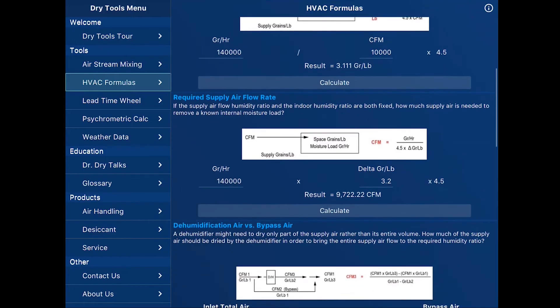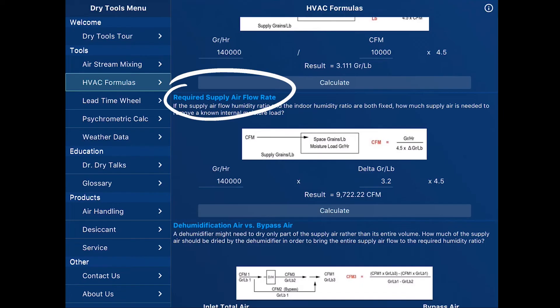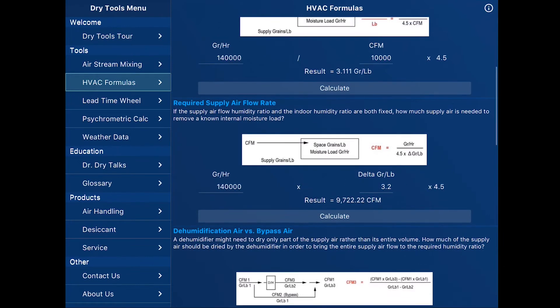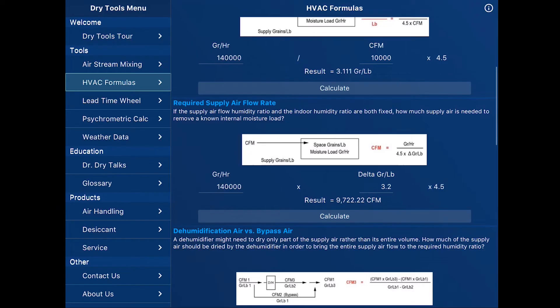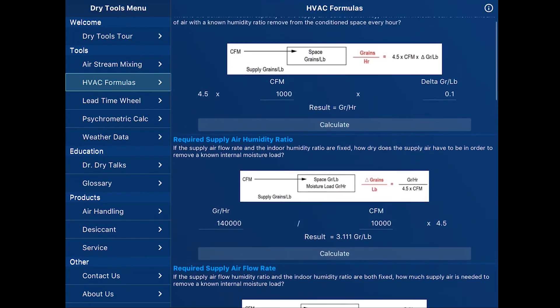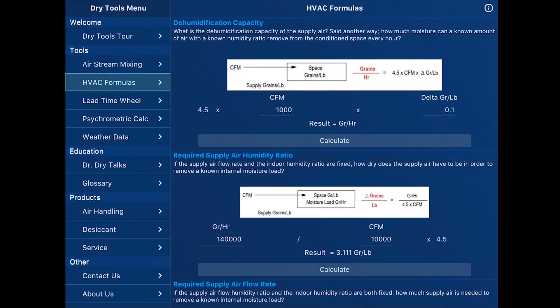Another formula, very similar to the one we just used, is to determine the supply air flow rate. I've typed in 140,000 grains per hour as our load, and our change in grains that we can apply to the space of 3.2. Press the calculate button and it tells me that at a 3.2 grain reduction, I need approximately 9,700 — or call it 10,000 — CFM. So there are several very useful formulas on this HVAC formula page.